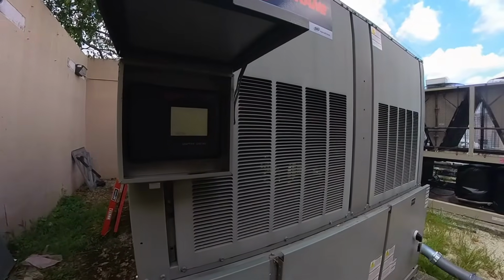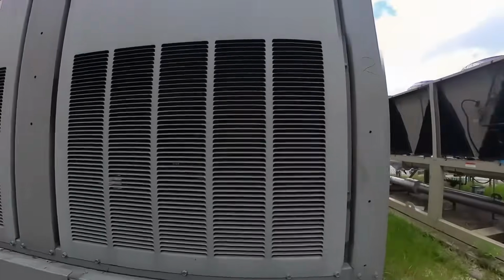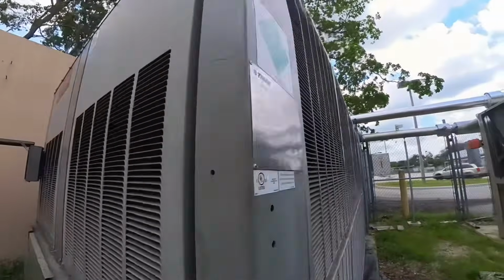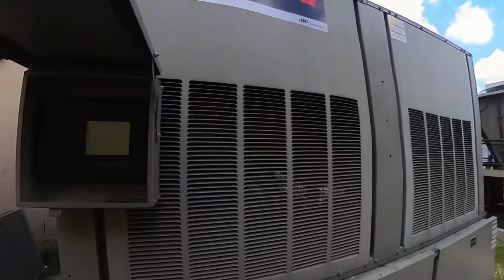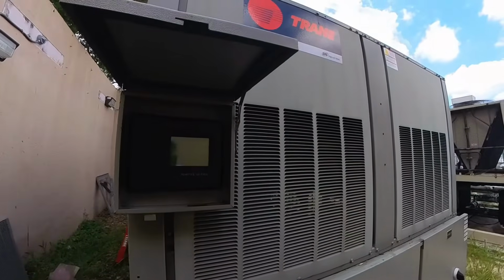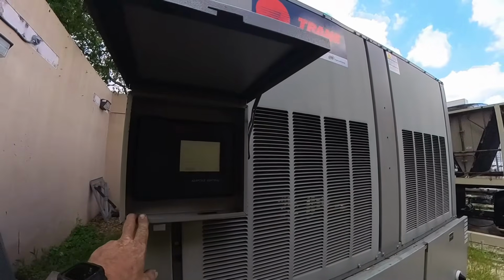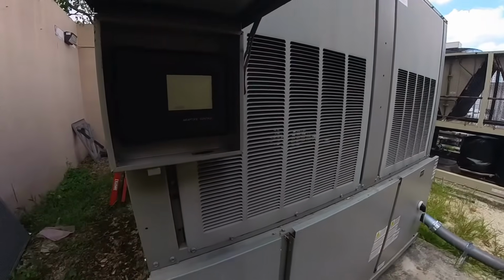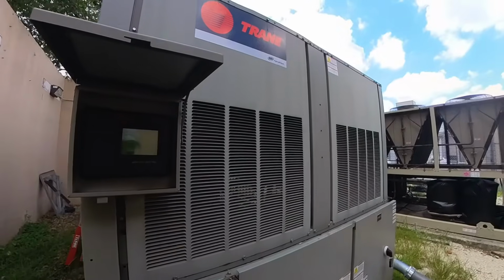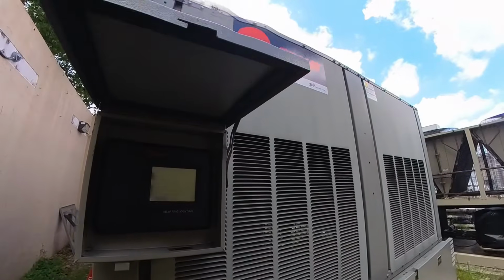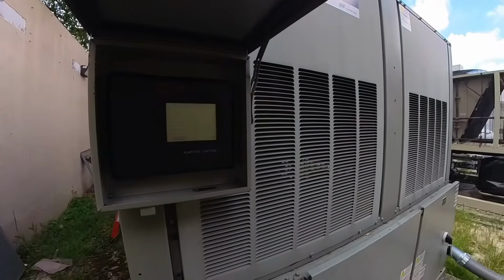Alright, thanks for watching. This was a Trane air-cooled, I believe it's 100-ton CGAM100. It was a suction temperature sensor that was bad on circuit 2. Replaced that, started back up, and found that issue with the condenser fan motor up there, which ended up being somebody else that had been here working on it, and they didn't tag it. So it is working now, but they're going to go ahead and replace the motor and shroud whenever they get it. But that's it. Alright, thanks for watching.